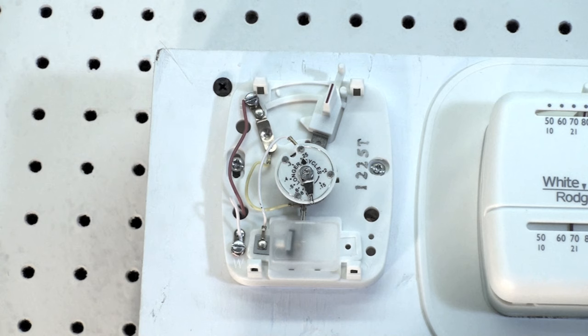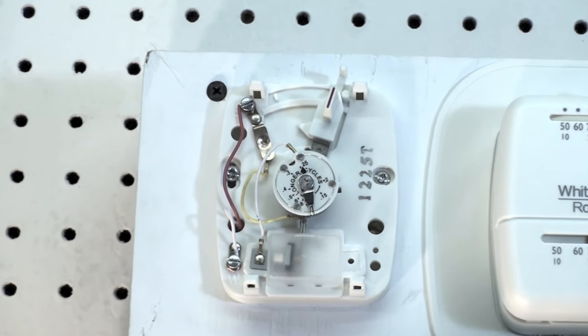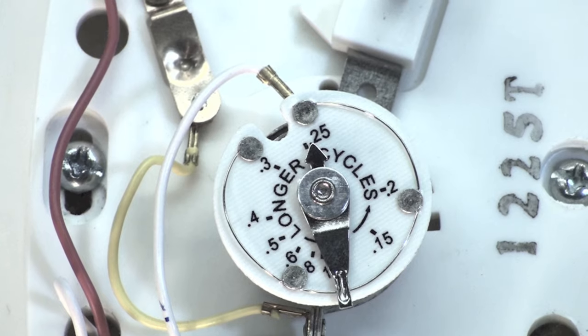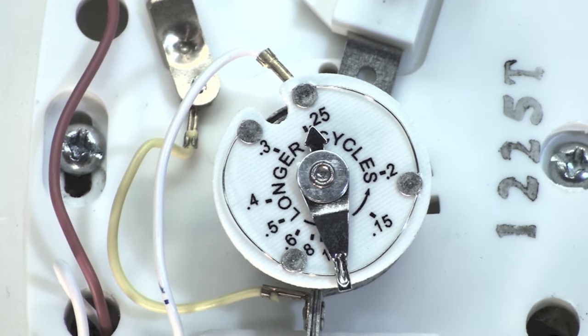Well, that's controlled by whatever you have in the control circuit. If your control circuit draws say two tenths of an amp, then I would go to the thermostat and I would set the dial so it says two tenths.